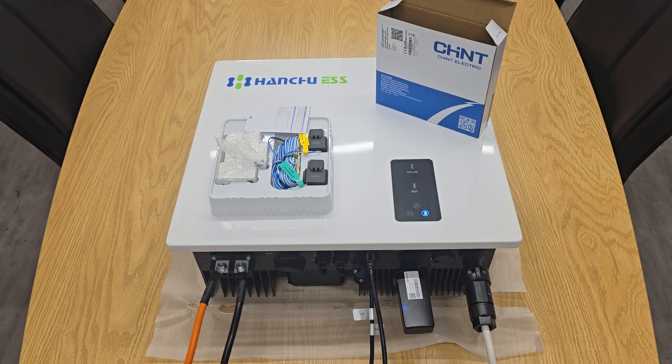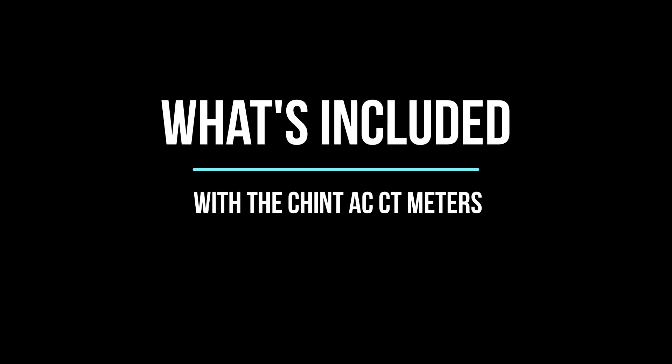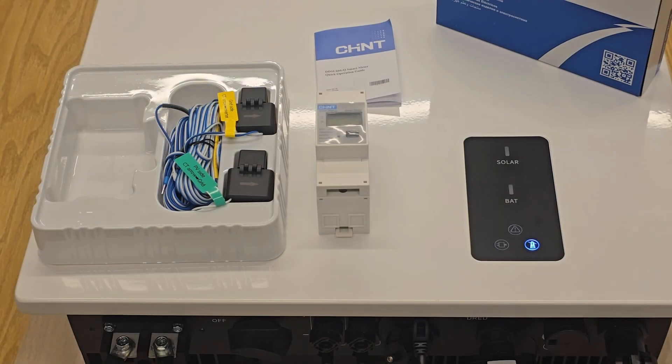Hi, it's Mick here from Infinity Innovations. In this video we're going to talk through the Chint CT meter and how to install this with your Hanchu hybrid, turning your hybrid into an AC controller. Inside the Chint box you have two CT clamps — one for the grid side and one to monitor the PV system already on the property. You also have the Chint meter, where the CTs will be wired in, and a data cable that goes from the Chint meter back to the hybrid. You'll also need to bring some power to the Chint meter.